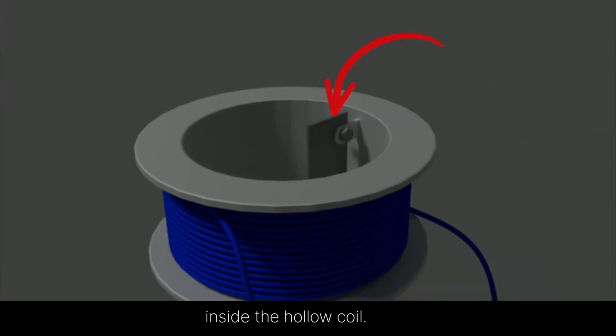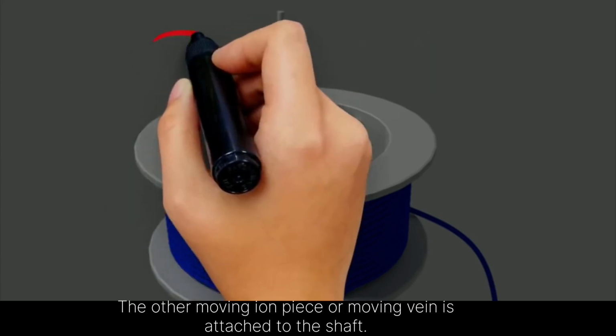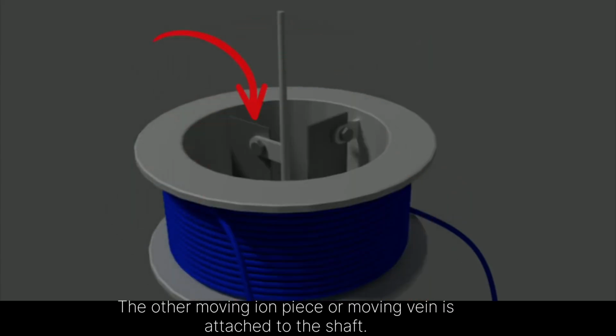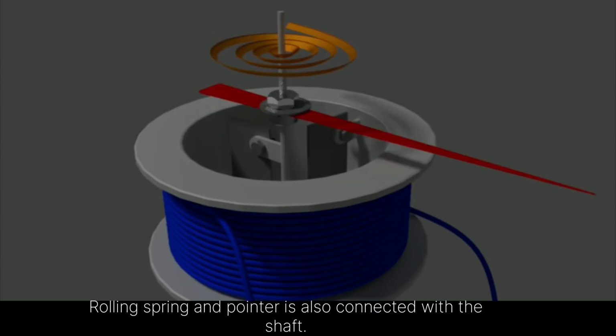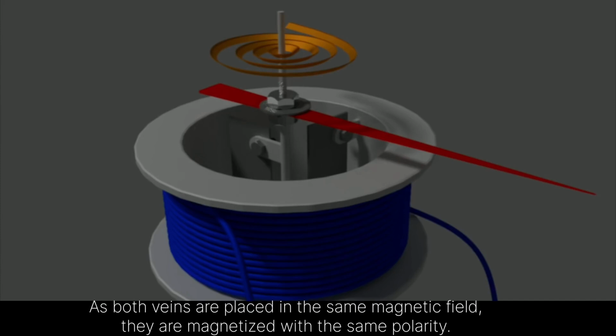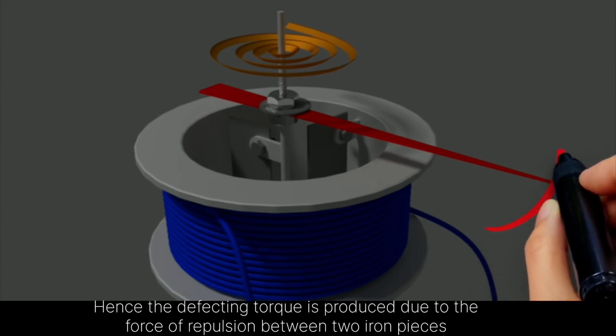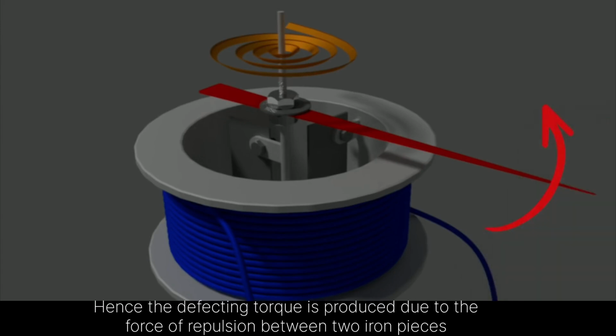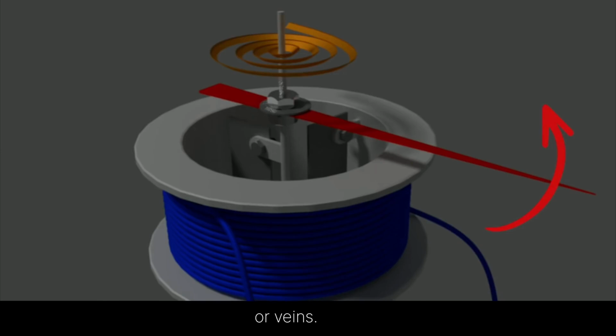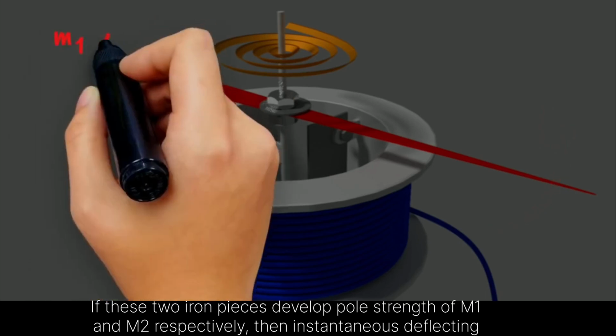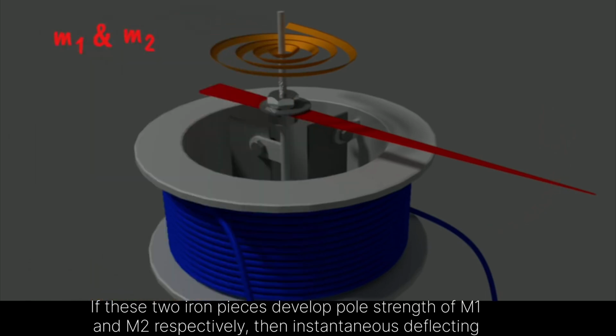In actual construction, a hollow circular coil is used, and one of the iron pieces is attached inside the hollow coil. The other, moving iron piece or moving vane, is attached to the shaft controlled by a spring, and the pointer is also connected with the shaft. As both vanes are placed in the same magnetic field, they are magnetized with the same polarity. Hence, the deflecting torque is produced due to the force of repulsion, with magnetic strengths M1 and M2 respectively.